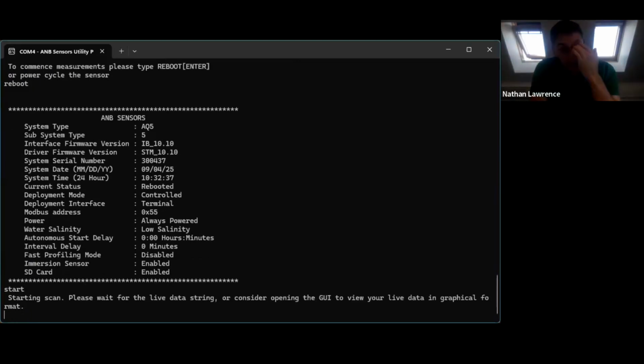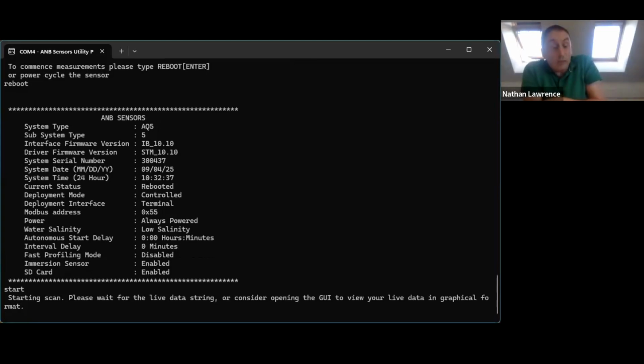So the sensor will now do its reference calibration check, understanding that it's in a low salinity condition, and then start to do the pH measurement and condition the electrodes as per the internal workings of the sensor through the abrade command. I think in fresh water this takes about 3 minutes, but the sensor is just setting all its internal settings, and then the first pH numbers will be given out.